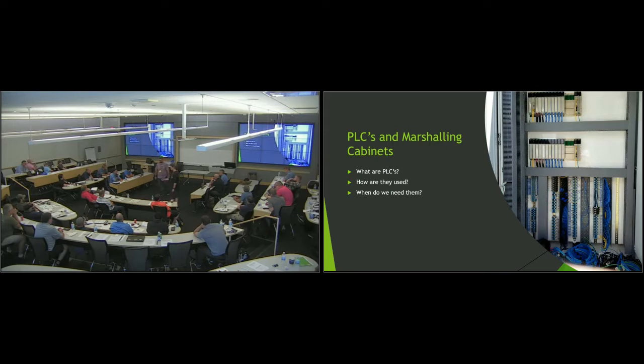Plus, my wrist right here is scrawny, but if I put this guy in the marshalling cabinet and he starts wrenching down on those PLCs, and one of those screw heads pops off or strips, can we buy another PLC input card, or can we get another terminal block? We could buy another input card, but you might not be on the job when it comes in, and they might not like that. So typically, everything is terminated to terminal blocks.